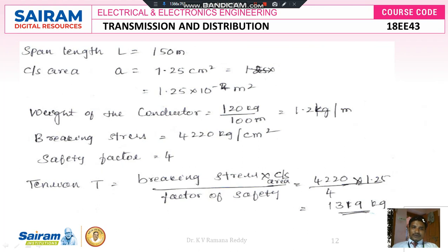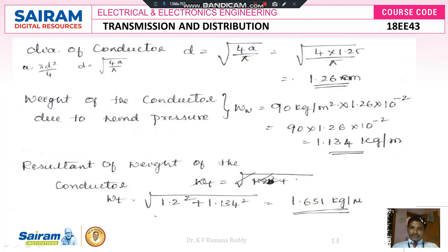Given: span length L = 150 meters, cross-sectional area A = 1.25 cm² = 1.25 × 10⁻⁴ m², weight of conductor = 120 kg per 100 meters = 1.2 kg per meter, breaking stress = 4220 kg per cm², safety factor = 4. Tension T = (breaking stress × cross-sectional area) / safety factor = (4220 × 1.25) / 4 = 1319 kg.